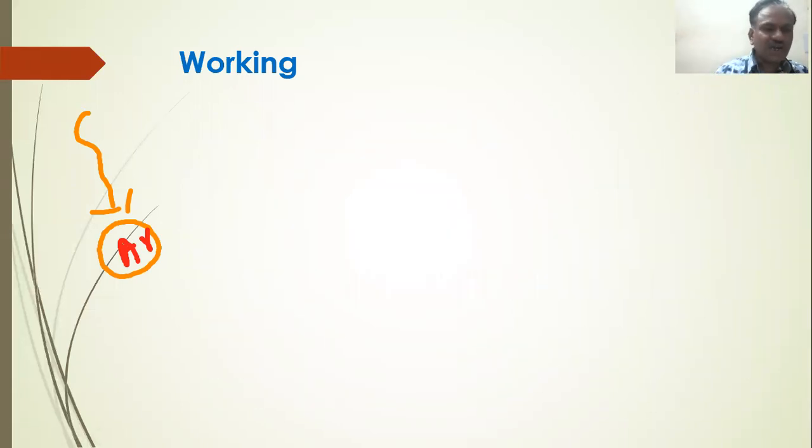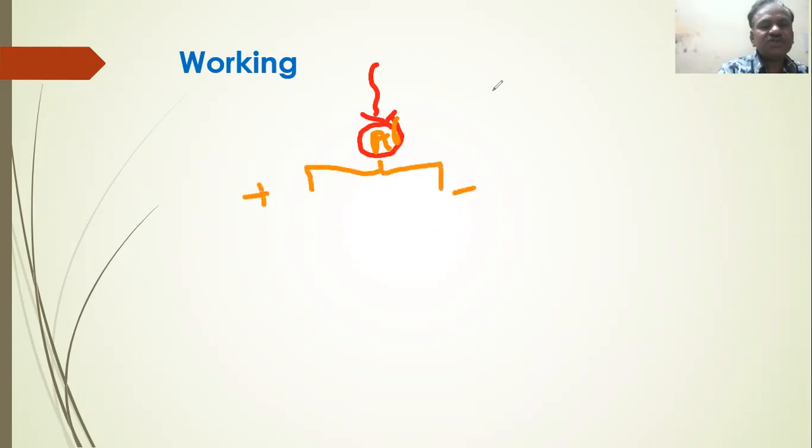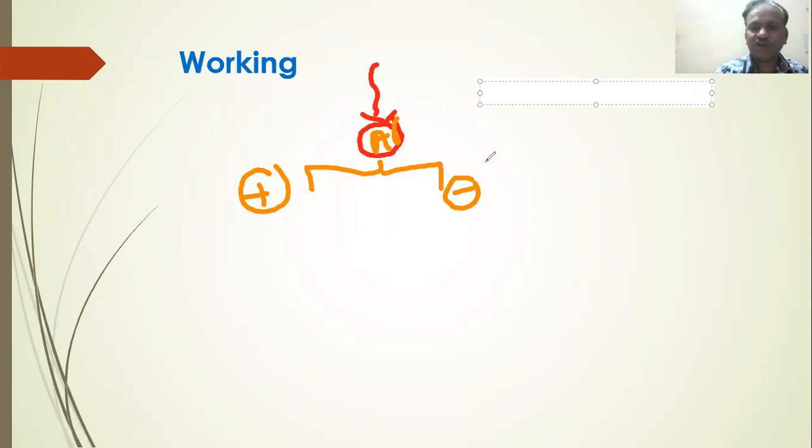Okay. First, this is argon, and the radiation is absorbed by the argon atom here. As a result, one is a positive ion and another is a negative ion, formed here. These electrons are there, no? This is called primary ionization.